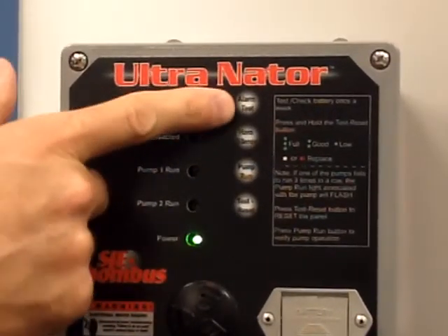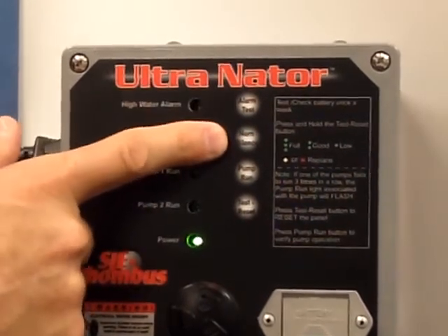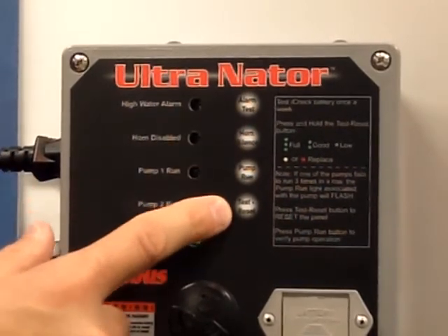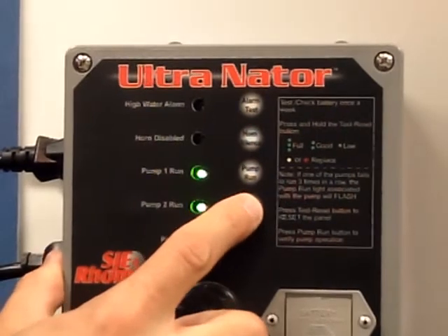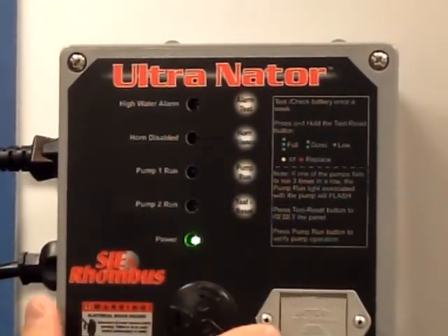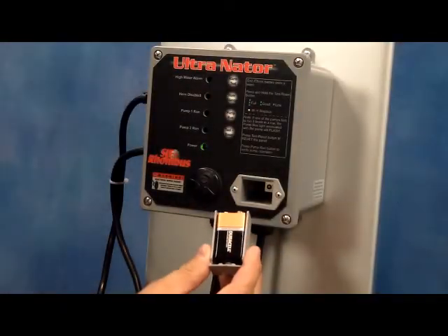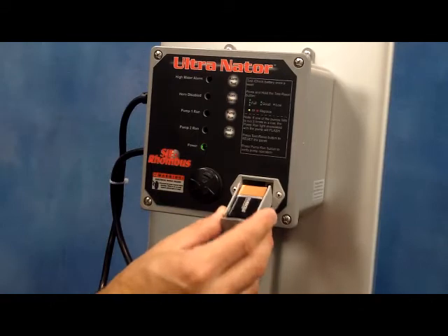The buttons on the Ultra Nator are alarm test for checking the alarm system, horn silence, manual pump run, and a test reset button. The test reset button can also be held down to check the life of the battery for the alarm battery backup. The Ultra Nator uses a standard 9-volt battery for the alarm backup system.